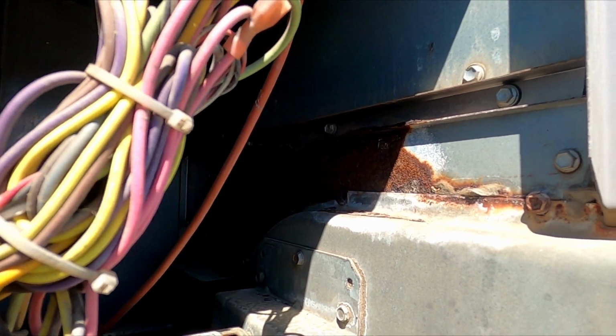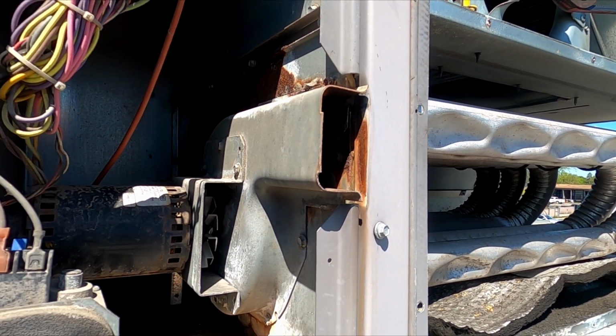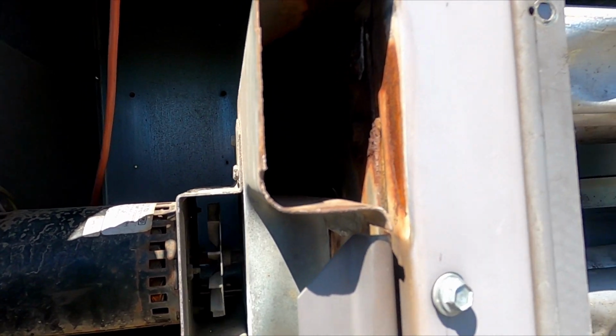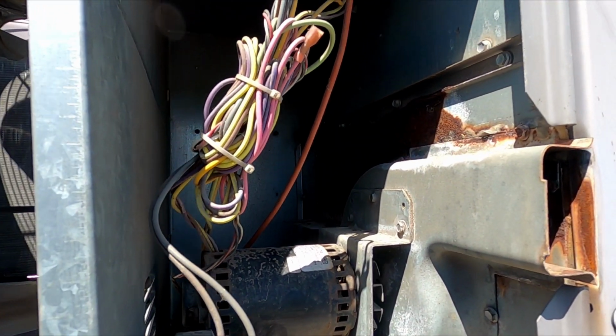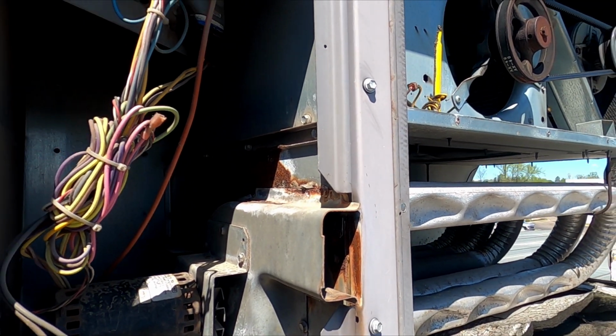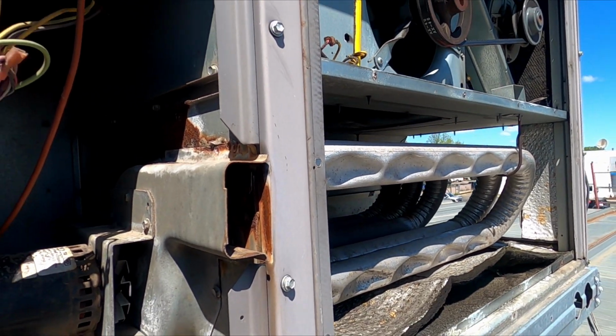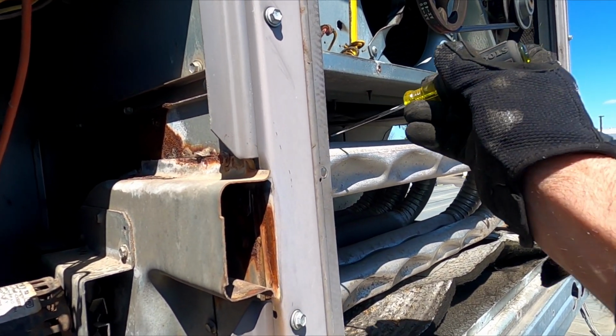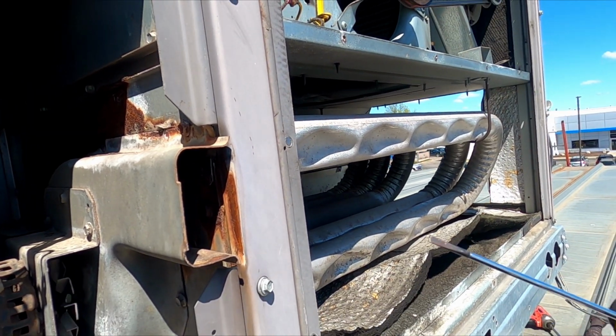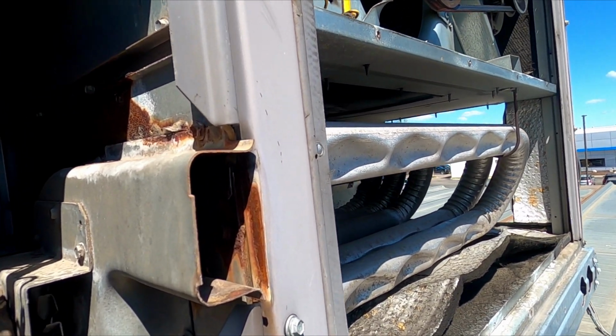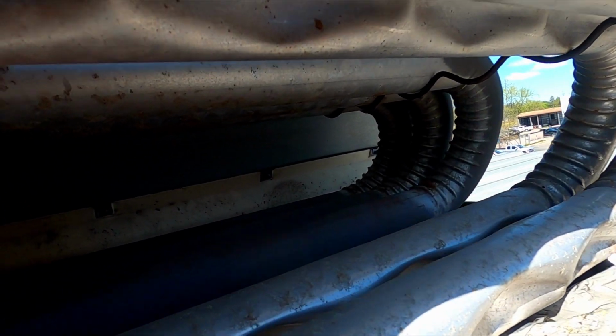Inducer motor needs to be changed, the heat exchanger needs to be changed. So that's how I check these Carrier heat exchangers—I just take my little screwdriver and scratch across little spots.